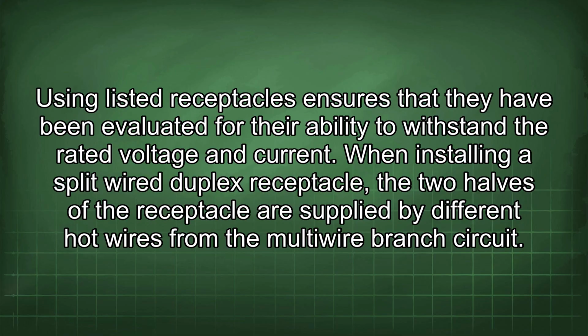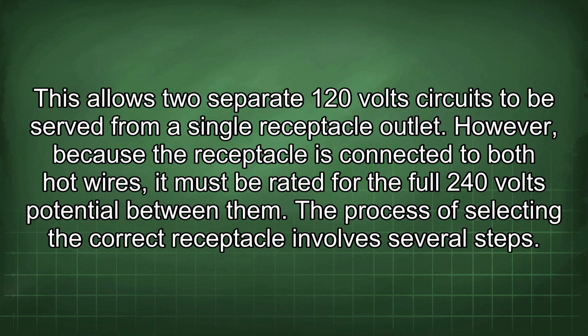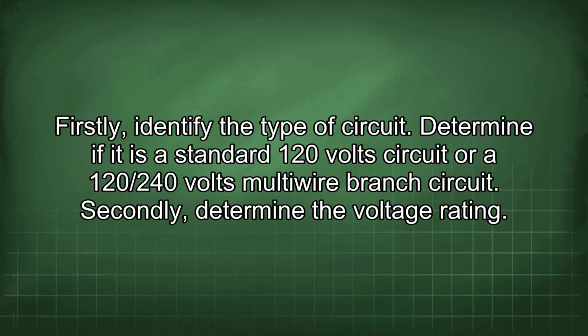When installing a split-wire duplex receptacle, the two halves of the receptacle are supplied by different hot wires from the multi-wire branch circuit. This allows two separate 120-volt circuits to be served from a single receptacle outlet. However, because the receptacle is connected to both hot wires, it must be rated for the full 240 volts potential between them. The process of selecting the correct receptacle involves several steps. Firstly, identify the type of circuit. Determine if it is a standard 120 volt circuit or a 120/240 volts multi-wire branch circuit.